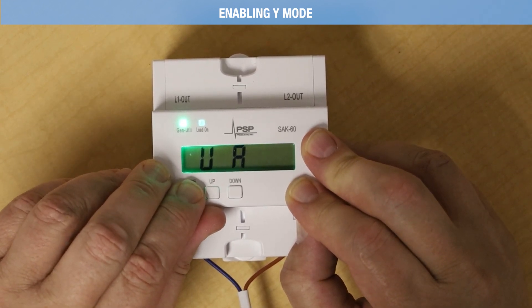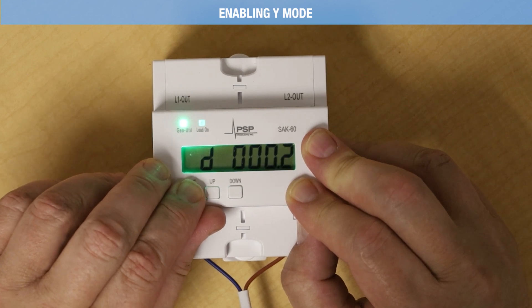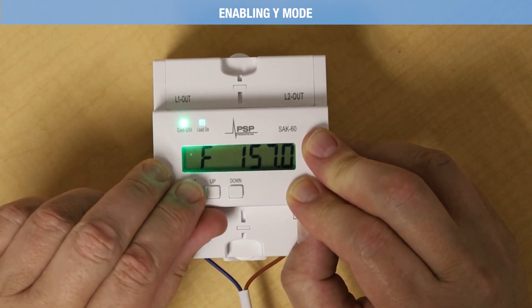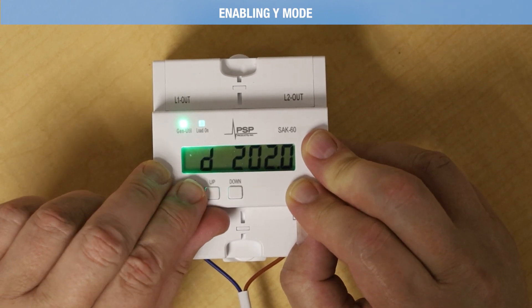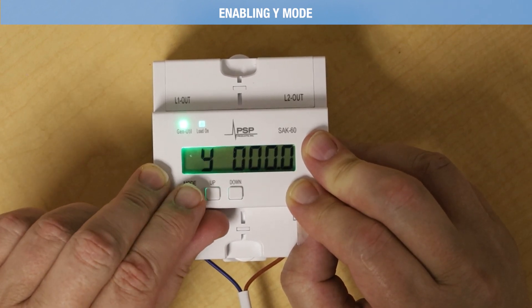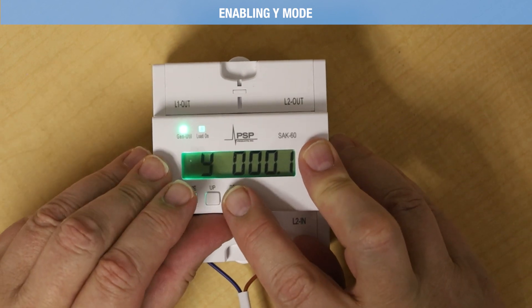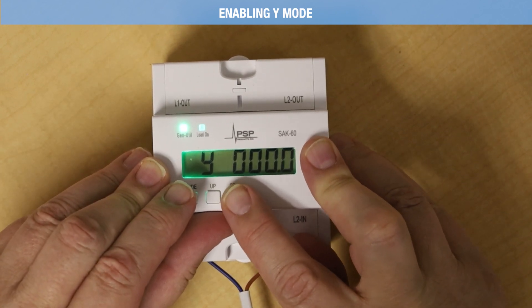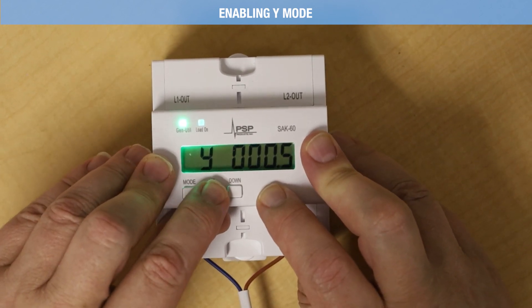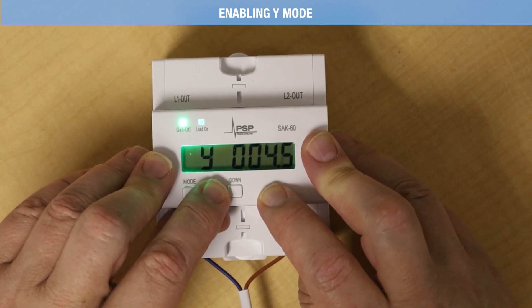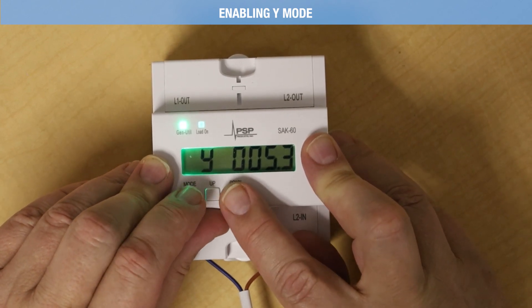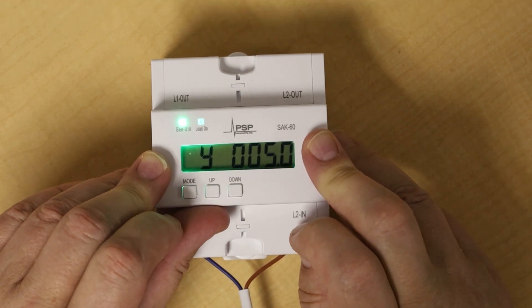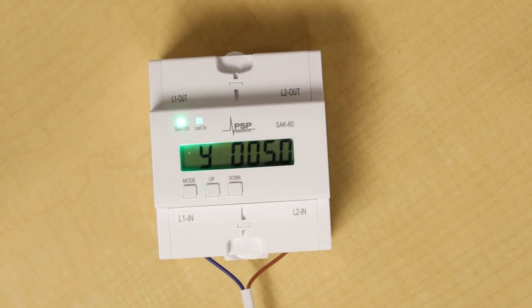Hold the mode button for 3 seconds to enter programming mode, then scroll all the way to Y. It's a lowercase Y that looks like a 4. Set Y to 5.0 minutes. You've now enabled Y mode, which will shut off the compressor upon return to utility power.